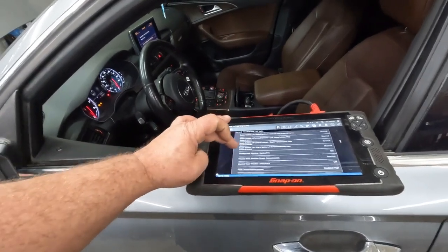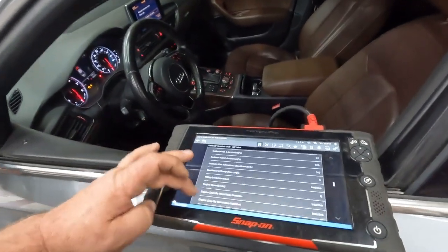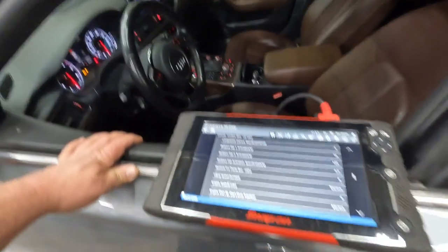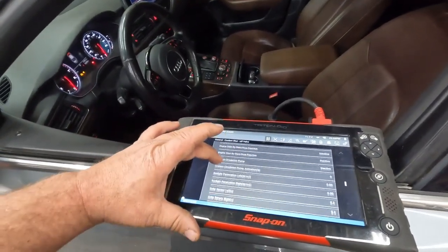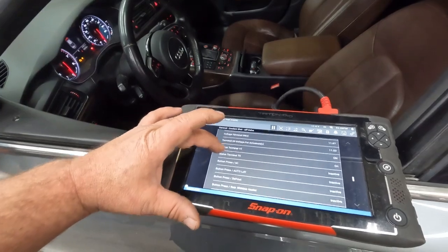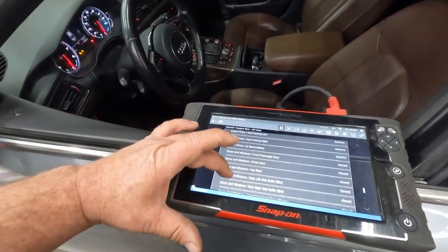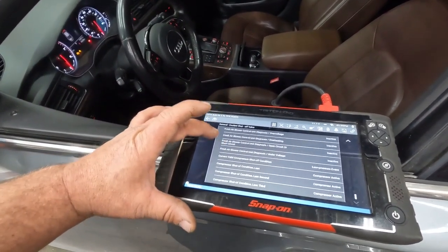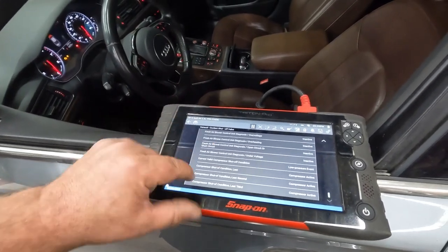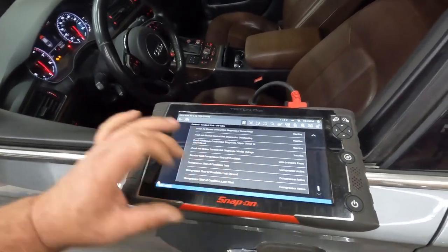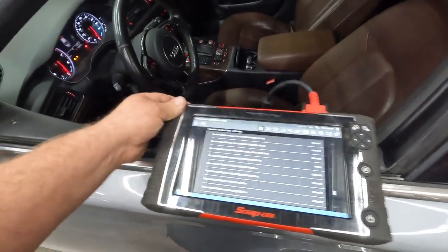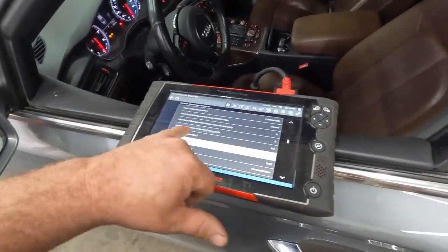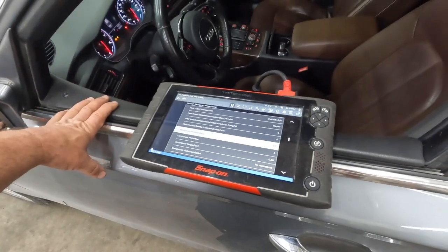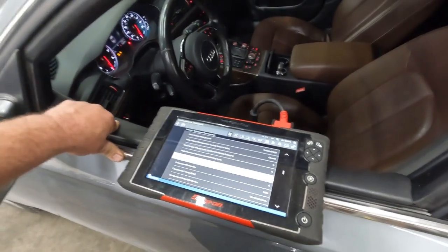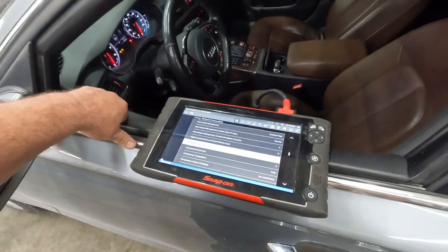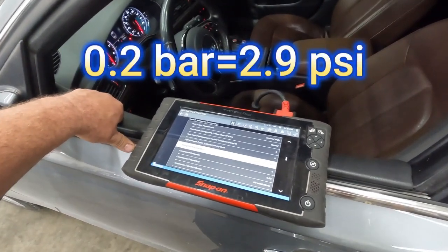Let's go into this one, it's just a little different. I want to see what kind of pressure it's saying we have in the Freon, or in the system. Low pressure event is the reason it shut off. So let's see here, refrigerant pressure - this is in bar, I don't like bar, but that's 0.2. That's very low. I don't know for sure what that translates to, but that's very low.